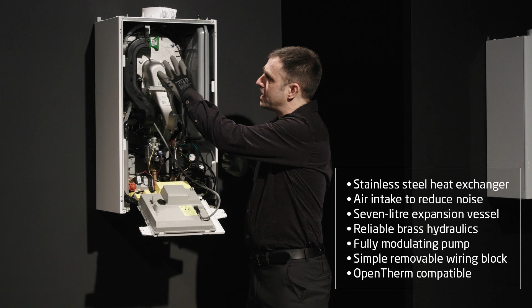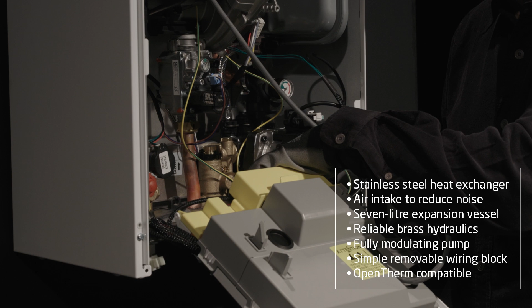I've also got a stainless steel heat exchanger, and I've got this air intake here, and this air intake reduces the noise of the boiler, making it a really quiet unit. I've also got a 7-litre expansion vessel, and looking down, I've got all brass hydraulics. We know this is tried and tested, we know it's reliable. Fully modulating pump for efficiency. And if I'm looking at the wiring, all I have to do is bring my wiring through the grommets at the base of the boiler and wire into my really simple wiring block here.